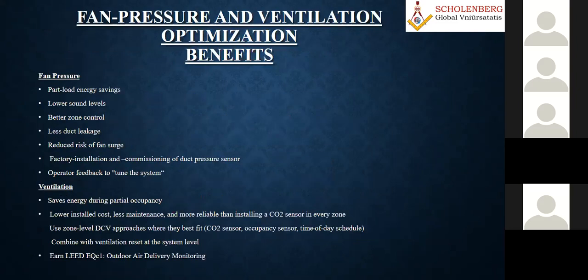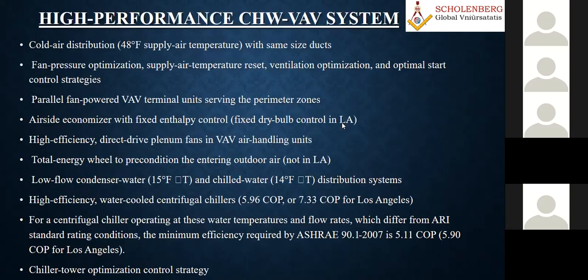Okay. So we completed how we have to optimize, particularly the fan pressures. I was also talking about the various types of fan selection and the ventilation, because ventilation load is very important in the heat load calculation also. So now we come to the variable air volume system combined with the chilled water.